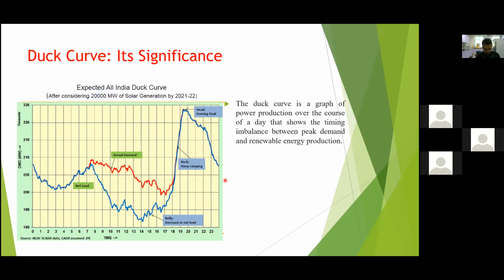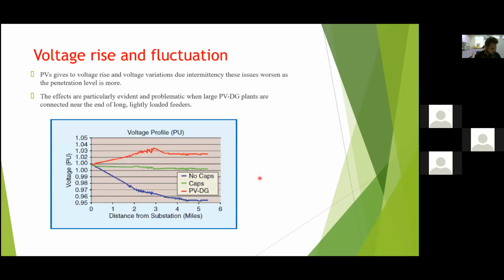So this large ramp is an issue and we need to handle it properly. Similarly, when you have solar rooftop penetration in the tail end of a feeder, you can see that there will be a voltage rise phenomenon. The voltage may be higher at certain points, and that large increase in voltage may create problems for the devices that are being used in the residence. Hence, caution is to be taken, and the voltage rise needs to be handled properly.